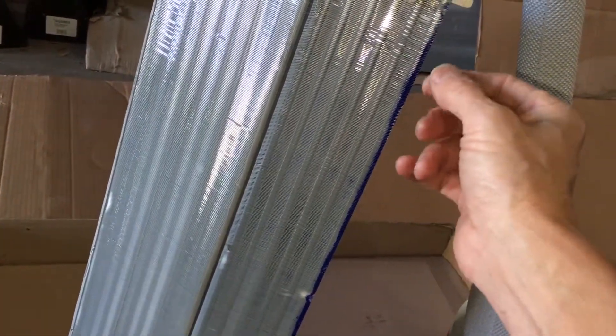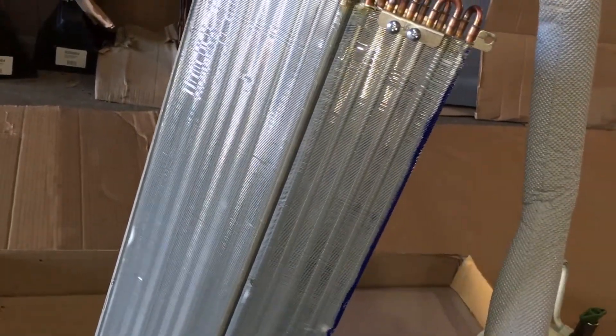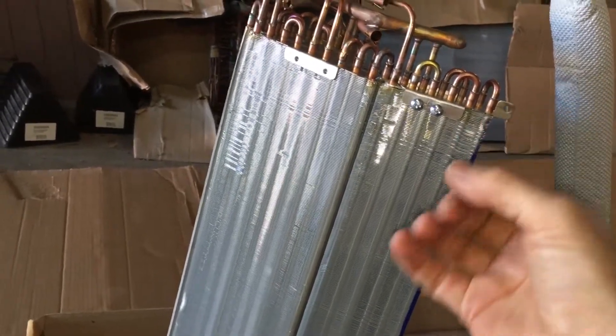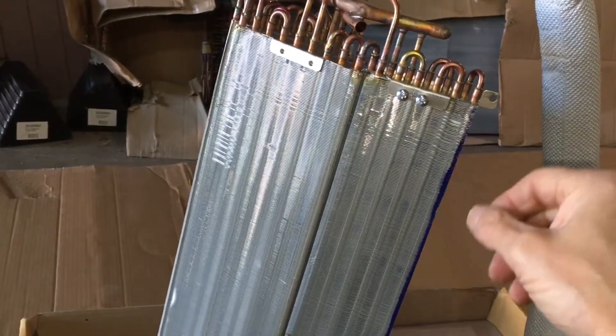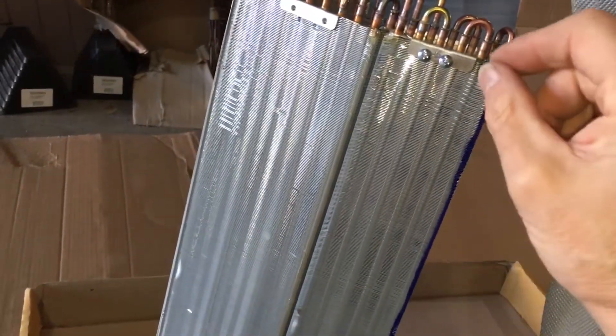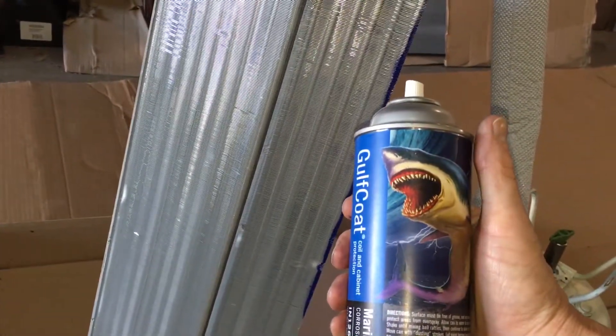You get that galvanic action going on — electrolysis eating away at the metal. You get solvents from your Windex, anybody using any cleaner with ammonia in it, or a chlorine molecule constantly attacking your copper, or sulfur. Over time you have premature failures.